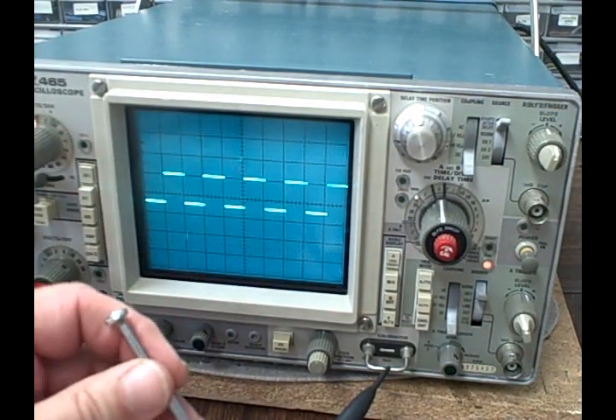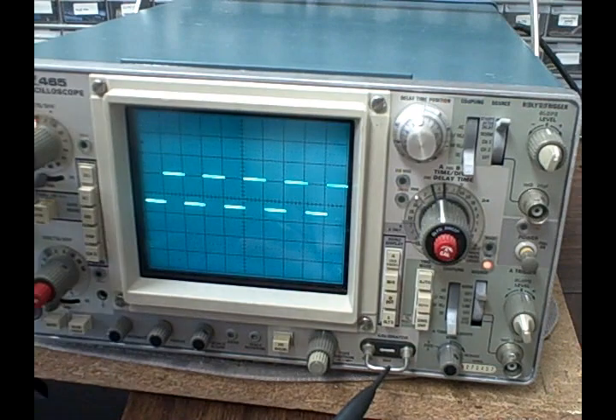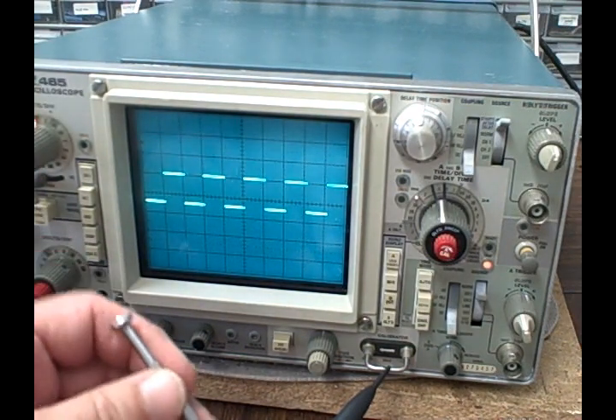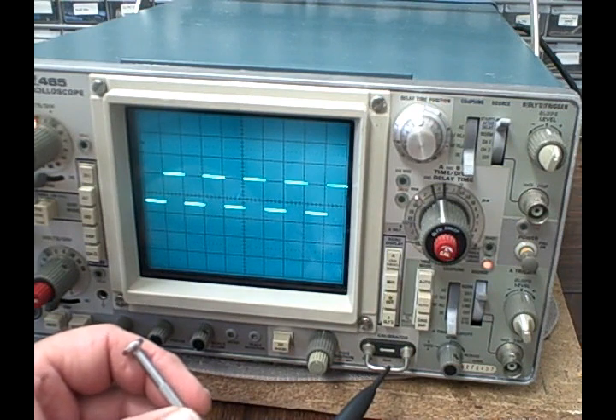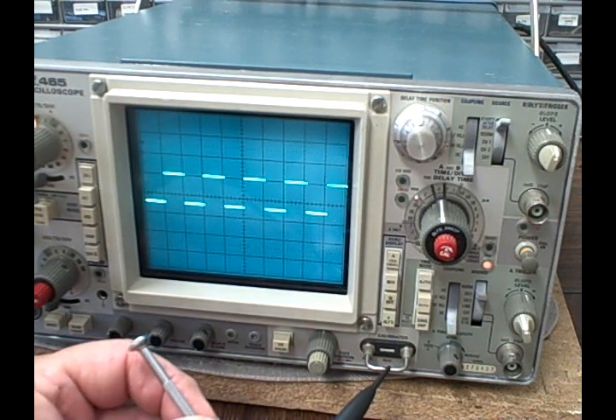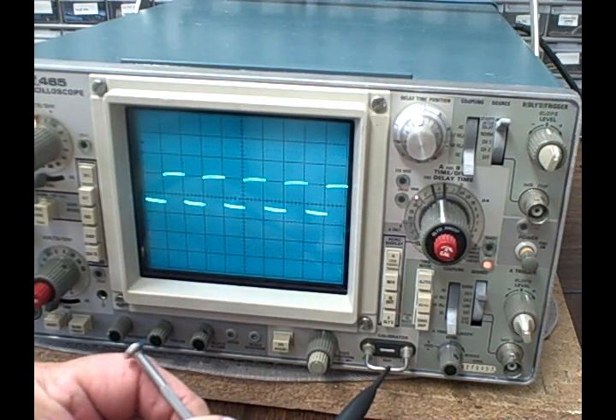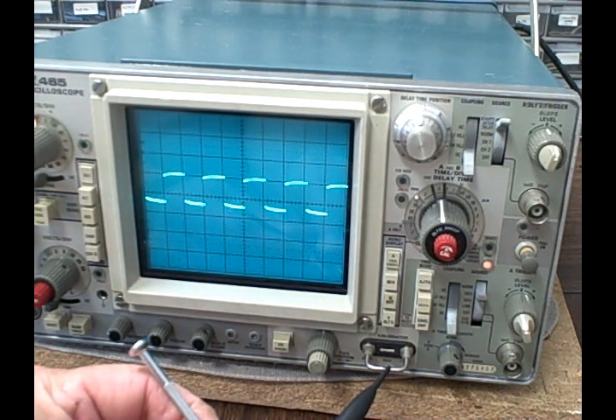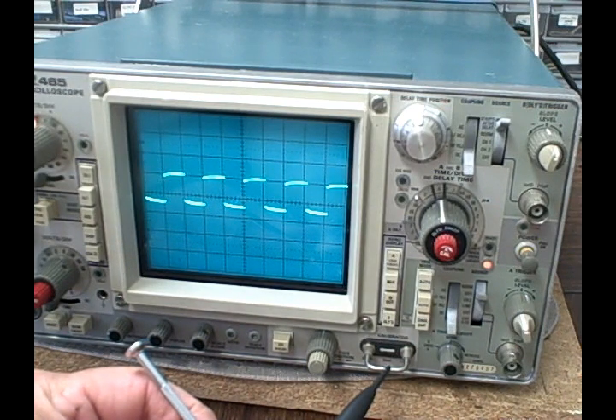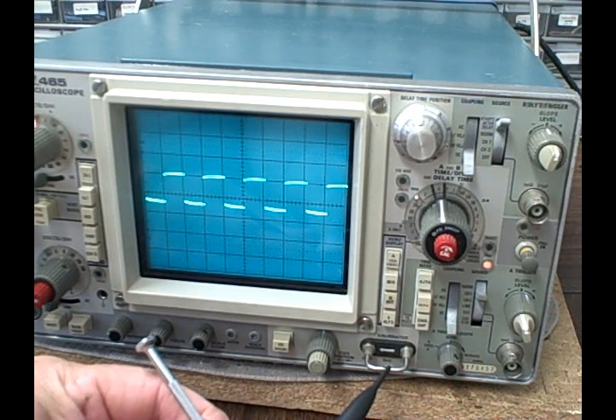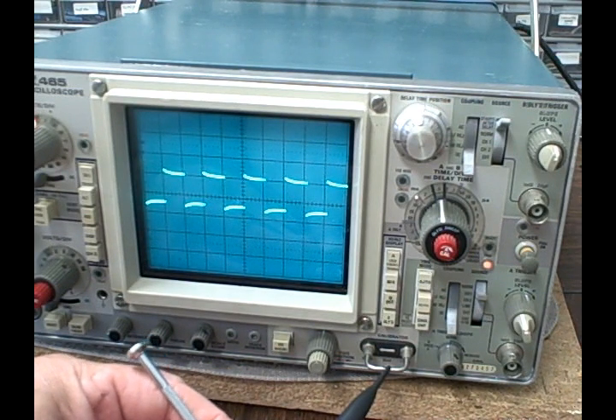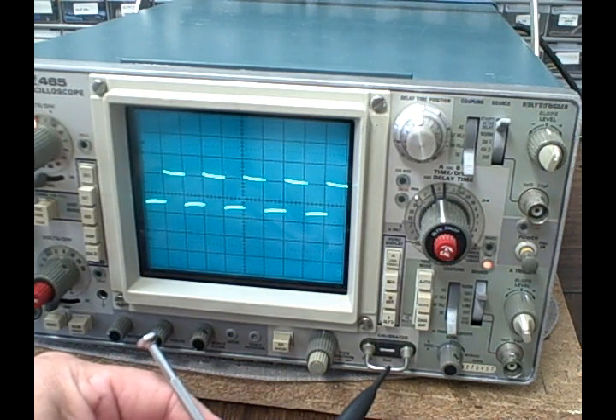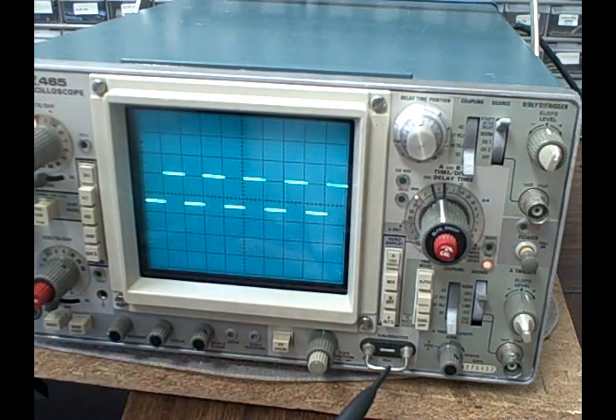Inside my probe, I have a little hole here. Sometimes it's on the bottom end of the probe, sometimes it's in the probe handle itself. This one's in the handle. And okay, I'm in it. So now you can see that my square wave is pointing down. That's undercompensated. There we go. This is undercompensated. The most square is where you want to be, and this is overcompensated. So I'm adjusting the capacitance to give me the best square wave. And I'd say that's pretty much it right there.